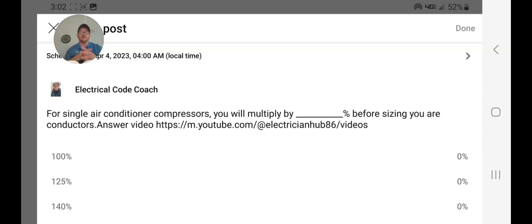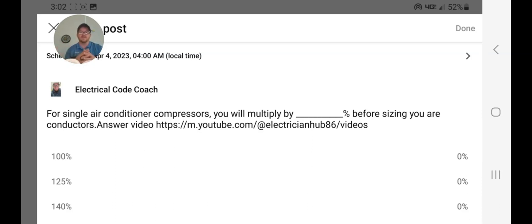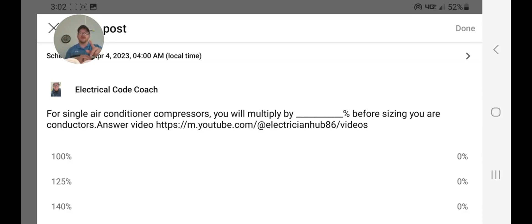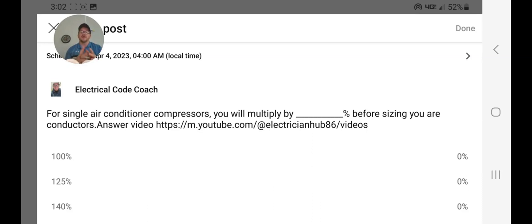The primary ampacity table is 310.15(B)(16) if you're in the 2017 code, and in 2020 and later it's Table 310.16. We would go down, likely in the 75°C column depending on the scenario, and select our ampacity for these conductors. This is a very broad subject, especially when dealing with ampacity and conductor selection.